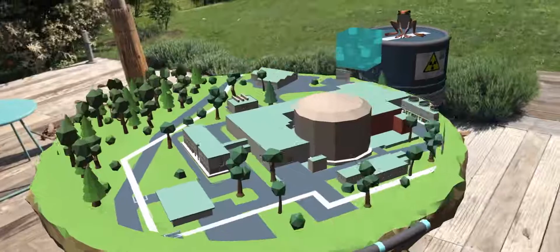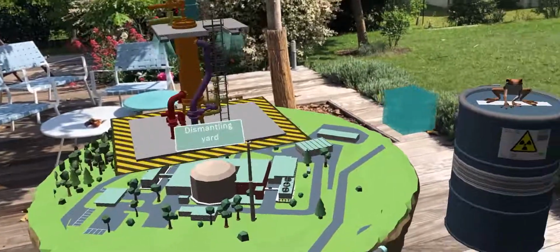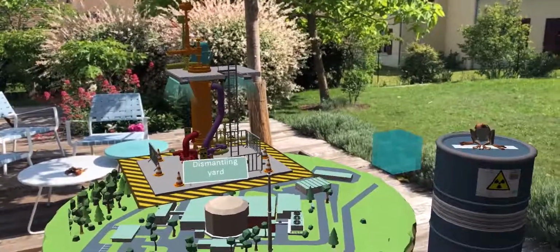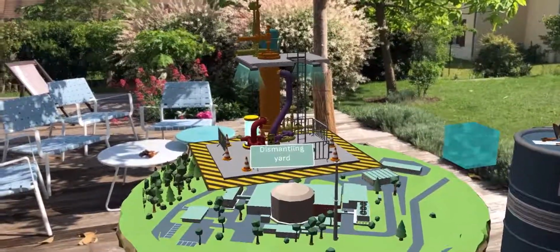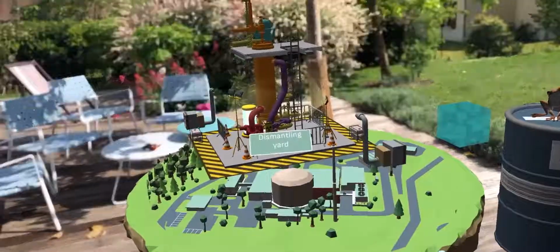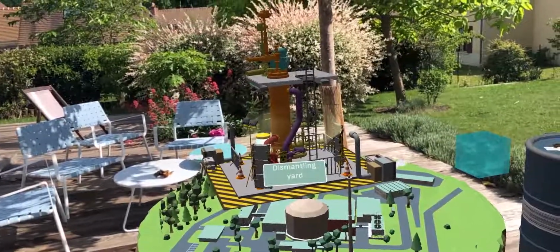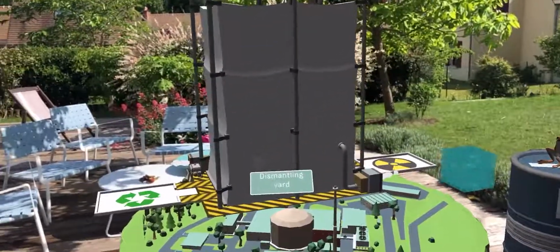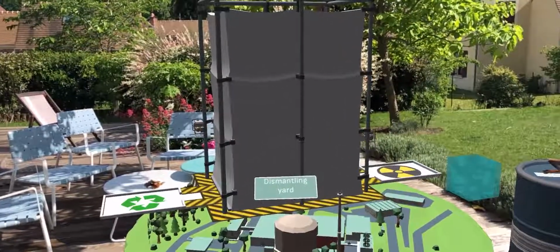Come with me and we'll see how things are getting on in the ESSOR reactor. First of all, the facility is being prepared for the work to be done, step by step, zone by zone. This is how the workyard is prepared. Enclosing the perimeter is the first task. Then all the residual liquids are drained from tanks and pipes. The electricity is disconnected and an autonomous power system is set up. Airlocks and local ventilation systems are installed. If necessary, concrete or even lead walls are erected to protect workers from radiation. Lastly, 2 buffer storage areas are created, one for radioactive waste and one for clearable material. Clearable means material not contaminated which must undergo exit checks.